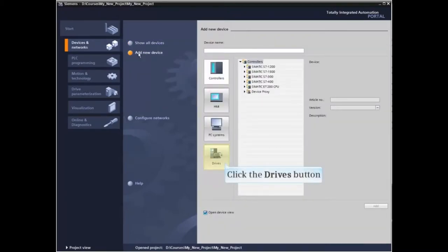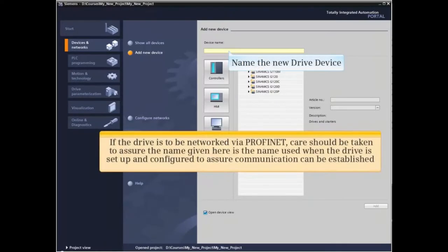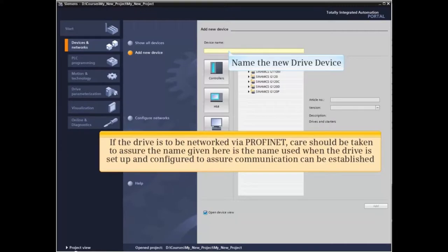Click the Drives button and name the new drive device. If the drive is to be networked via PROFINET, care should be taken to assure the name given here is the name that will be used when the drive is set up and configured to assure communication can be established.